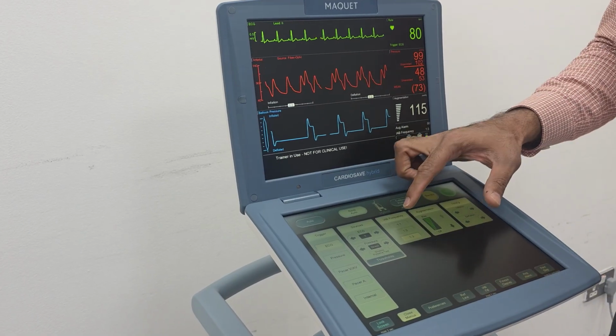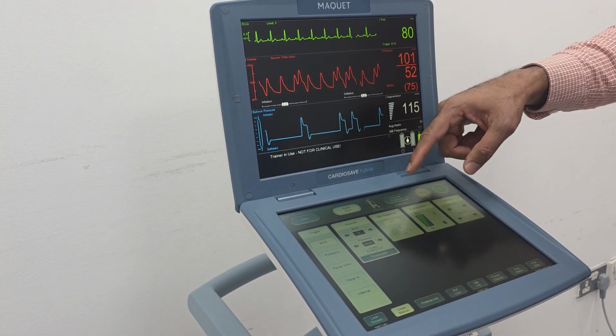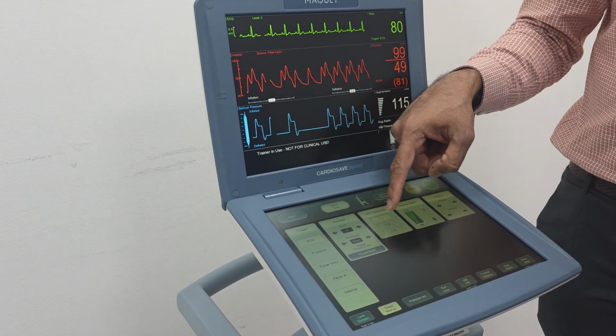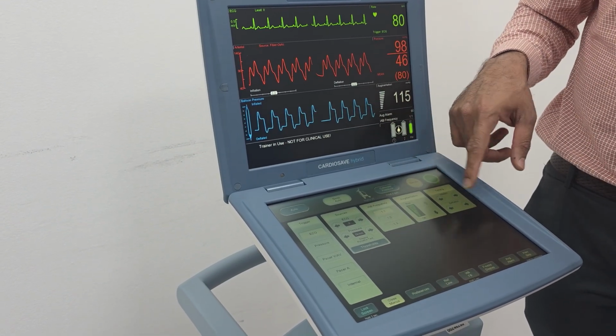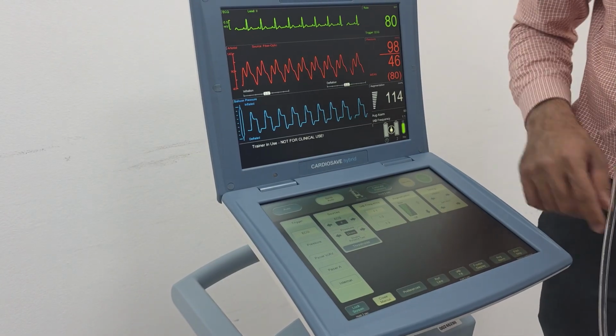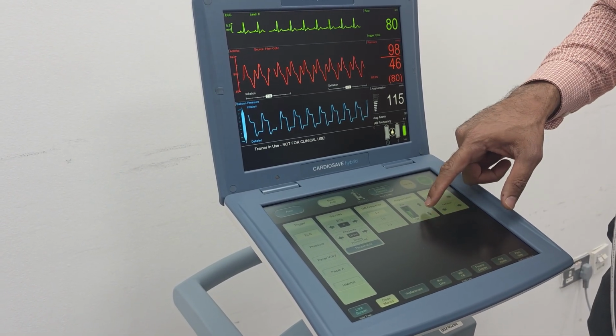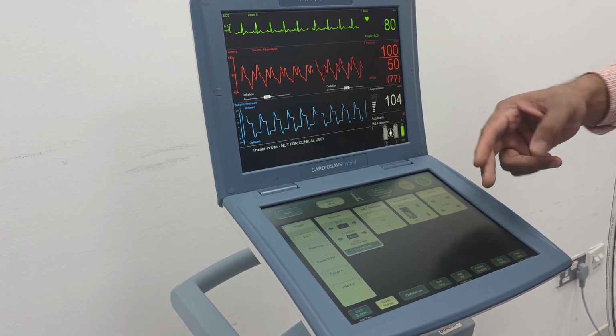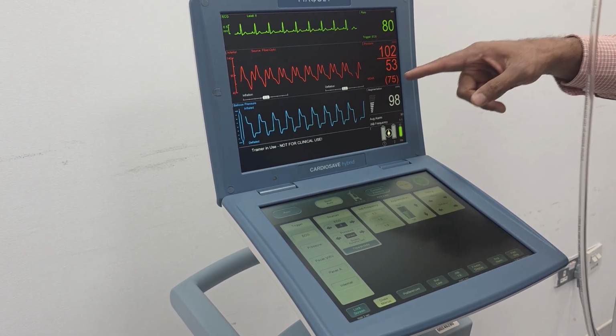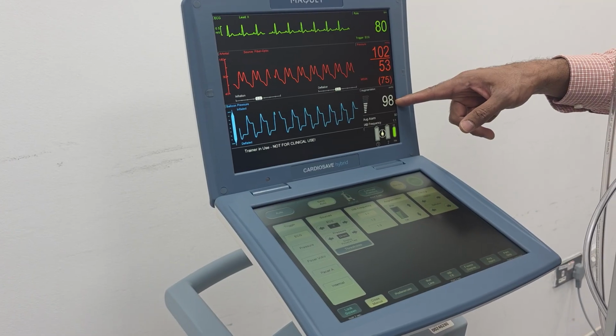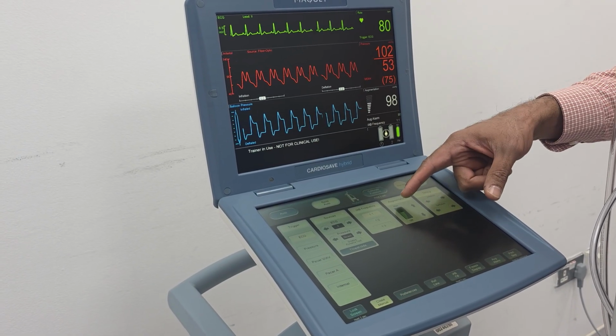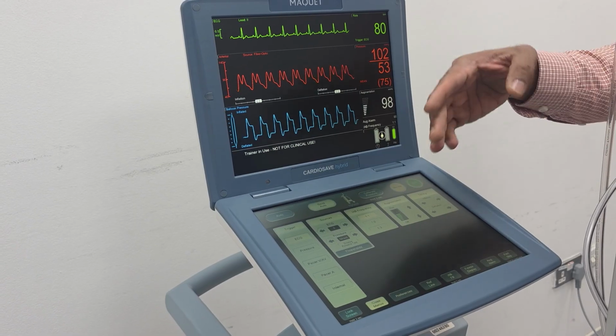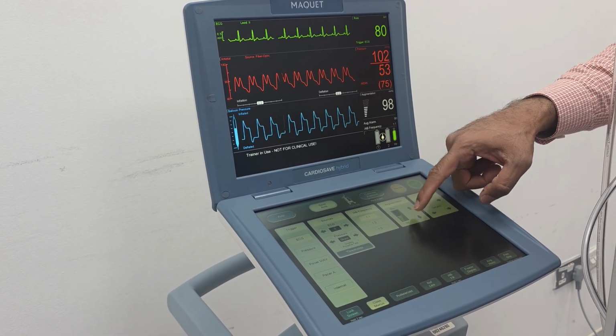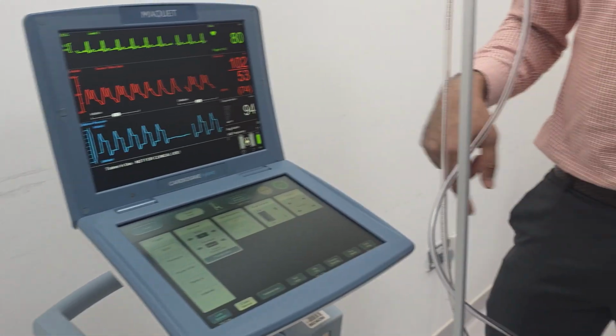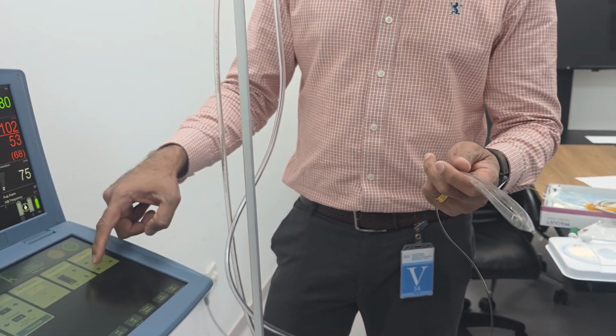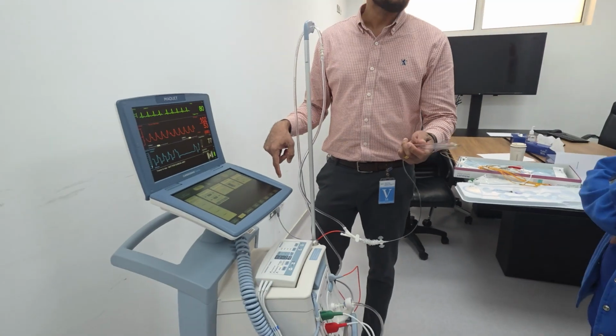During the weaning stage, same like CS300, either you will use frequency or you will control the augmentation. Augmentation means the balloon maximum pressure. Okay, we can also control this one to reduce it. During any stage, you can control one of them or both, see how the patient is reacting. So the pressure I have reduced, so the augmentation is reduced. But we are also recommending don't go more than 50% for more than 30 minutes because of thrombus formation. If we are reducing it, let's see, it's not inflating. So there could be a thrombus formation. Okay.